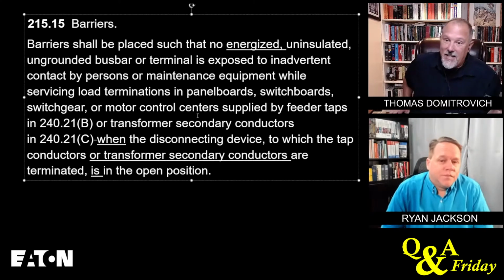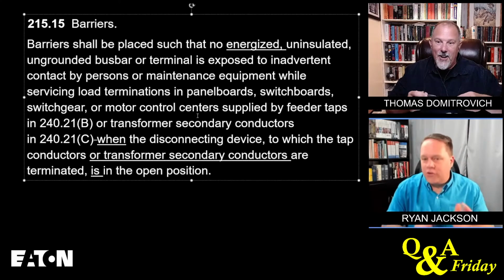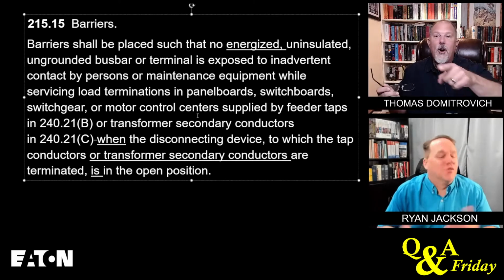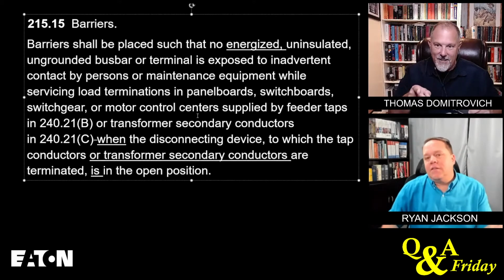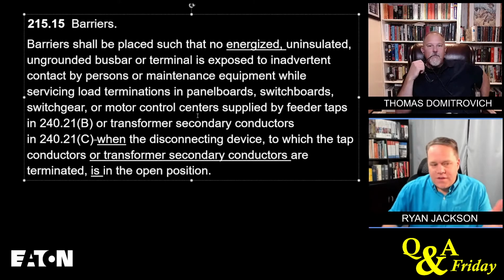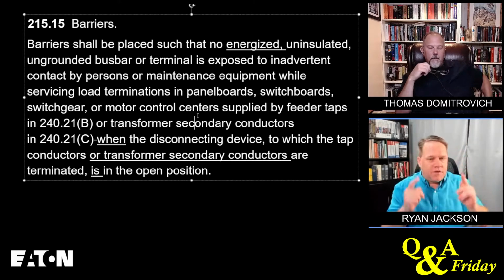Not all transformer secondary conductors are tap conductors. Almost all of them are. All of the common ones that we see, right? When aren't they? When would you say they're not a tap conductor? Okay, well, when people think of a tap conductor, usually they're thinking of a big wire and we splice a couple of smaller wires to it, and those smaller wires are tap conductors. Right. And indeed, they probably are. But when you look at 240.2, it's a beautiful definition. A tap conductor, in 240.2 in the 2020 and previous editions, and Article 100 in 2023. But the definition of a tap conductor is a conductor that's not a service conductor. So we can't have a tap conductor service conductor.